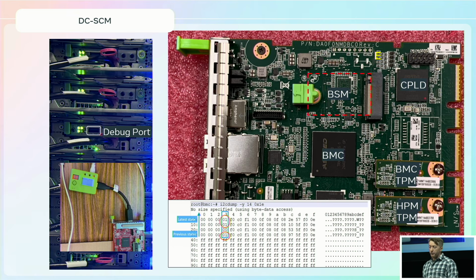In that same vein, what we're finding in these larger AI systems, with a lot of domino effects or potential domino effects, is the need for robust logging. So we have a handful of management CPLDs spread out across the system, typically monitoring power rails, looking at temperatures, and leak detection—they have a very good low-level view of what's happening. We've implemented what we call a flight data recorder functionality, where throughout the life of the CPLD, in its own internal non-volatile flash, it logs the state machine changes as it goes through.